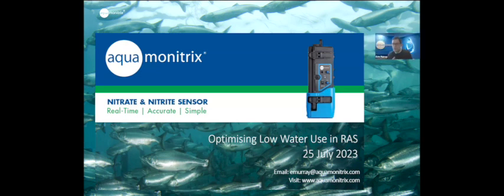Yeah, that's a good point, Mike. So I touched on it briefly there in terms of the selectivity. Because we have our anion exchange separation within the system, in combination with our specific wavelength LED, it's highly selective for nitrite and nitrate.